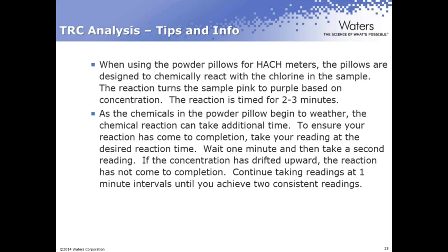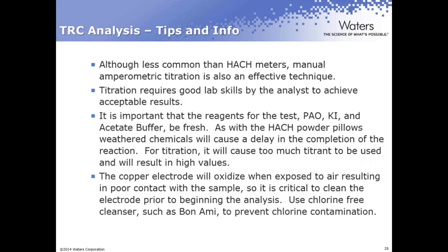So what I do is I tell people, well, if you have more sample left over, rerun that test, and I talk to them about the process of waiting a minute and an additional minute until they get their acceptable, consistent readings. And then I say, does that consistent reading fall within your range? And 99 times out of 100, they say yeah. So please keep that in mind when running that.